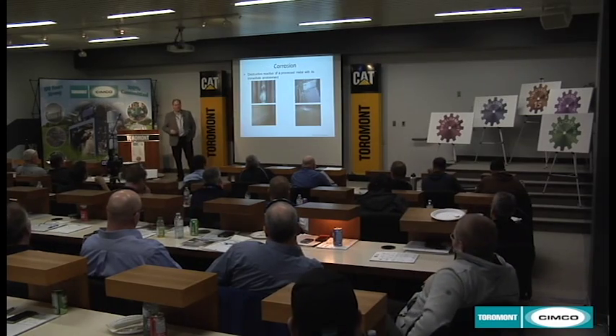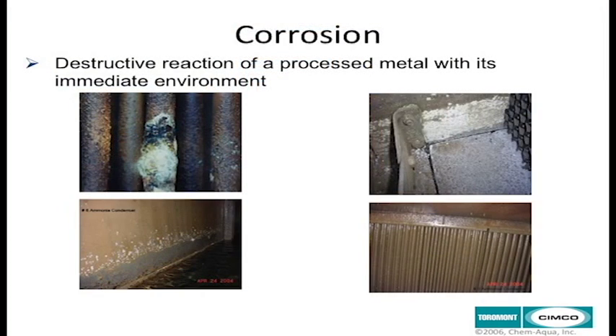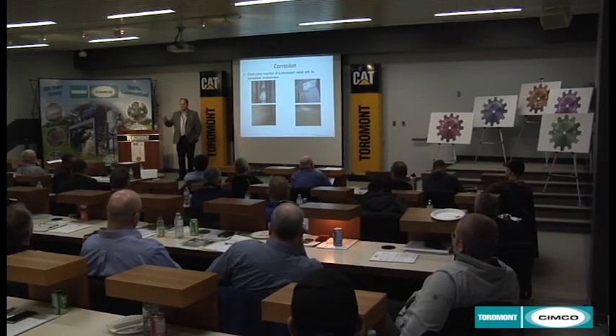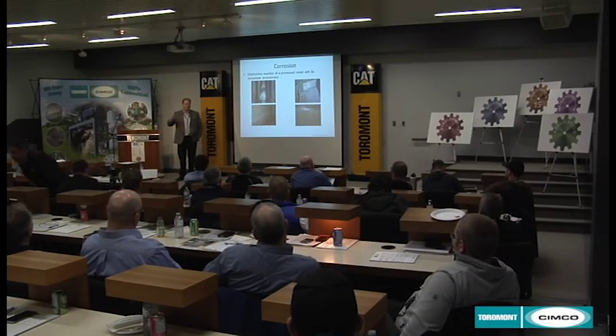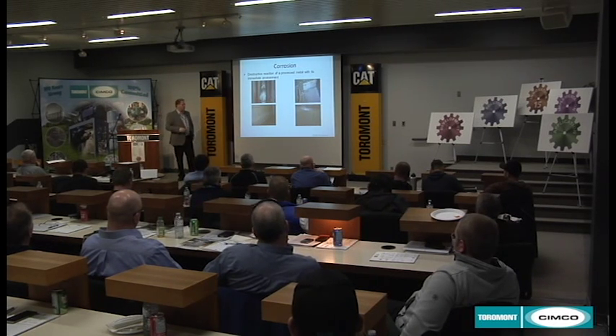Corrosion. It's not often found in evaporative condensers, but it does occur. What types of corrosion? Sometimes you get a blister on a condenser pipe. If you get a leak of ammonia out of the condenser tube inside your evaporative condenser, you'll have very active corrosion in that area. What causes corrosion?